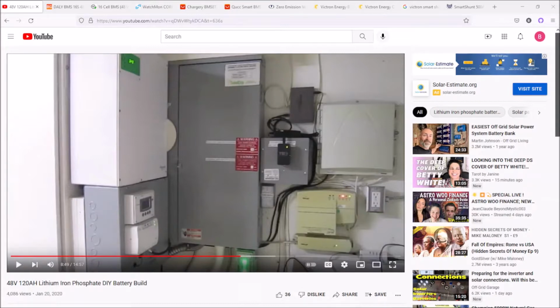Stack inverters, maybe put an 18 kW Sun Gold. Now you've got a 20, 25, 30, 40, 50 kilowatt hour battery. You've got to manage 300, 400 amps, maybe 500 amps worth of power. I'm specifically referring to the type of battery management system that you'd need to use. Basically, they fall into two categories. You've got the all-in-one type.